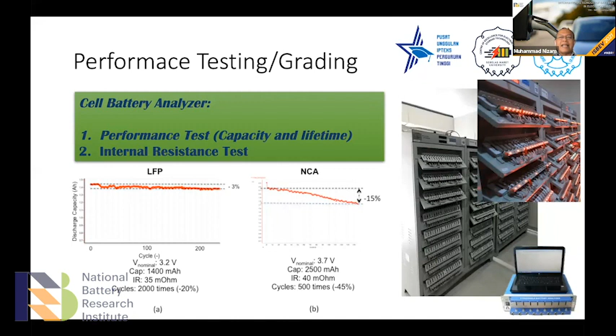We have to monitor that, and also do the internal resistance test. In this performance testing or grading, we can see the cycle of the battery, the capacity of the battery, how much the battery's performance goes down or up to, for example, 2000 times, and what is the IR. This is important to make sure the battery is suitable for EV or for ESS, energy storage system.